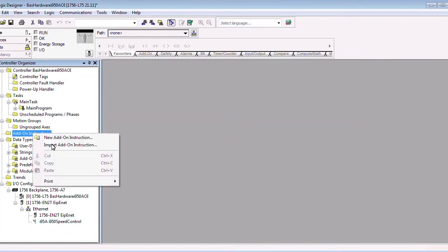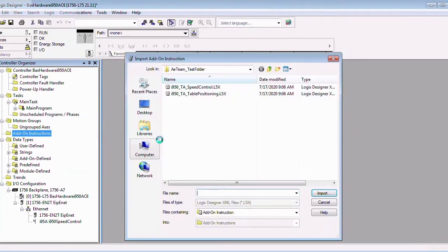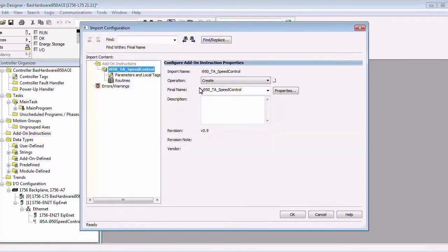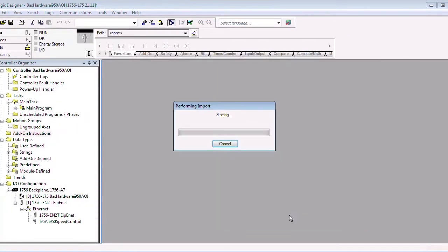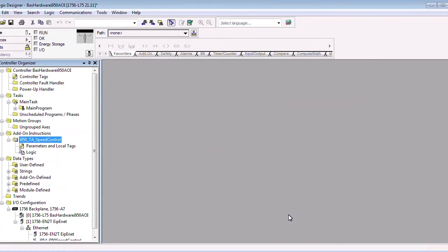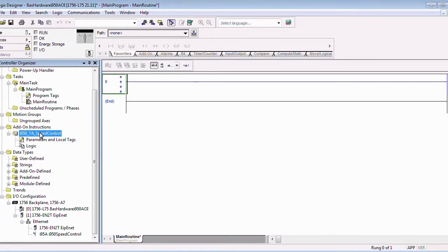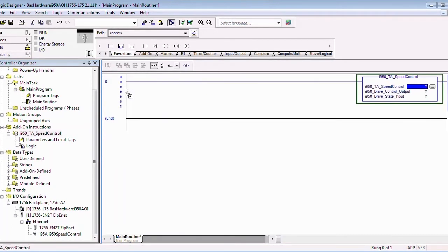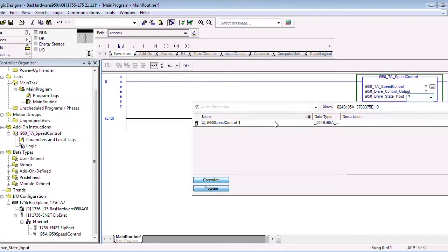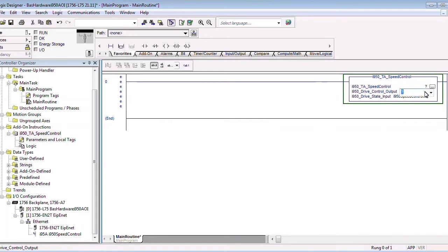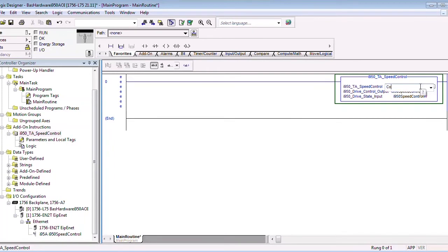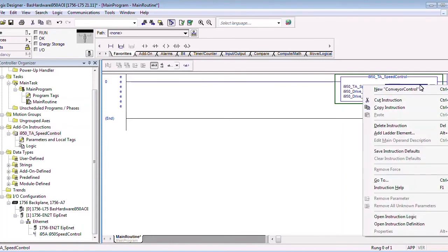Lenze also developed an add-on instruction, or AOI for short, that will make it easy to interface with the i950's speed control functions. You can import the file into the add-on instructions folder in your program tree. Other than the speed control AOI, Lenze also developed or is in the process of developing other types such as the table positioning AOI. In your main routine, you can drag the AOI into the rung you will be using for the i950 control. Then assign the inputs and outputs to the i950 you added as a module before. You can assign or create a new tag for the AOI, doing this for each axis. Just remember to create a separate tag for each.